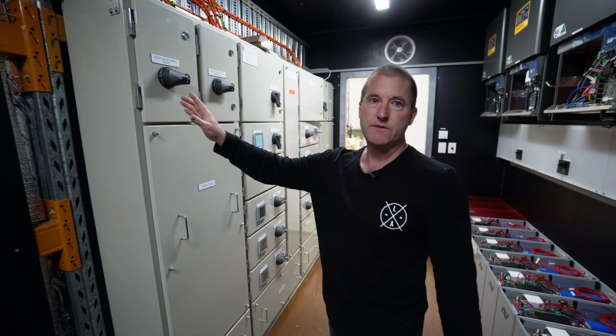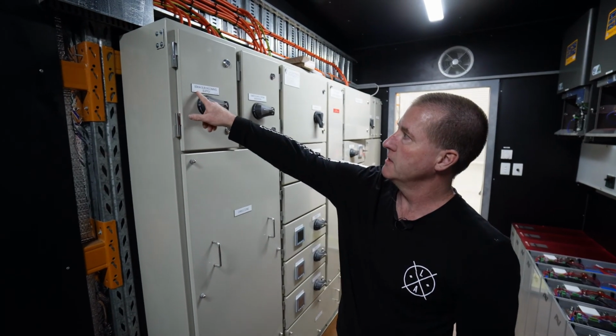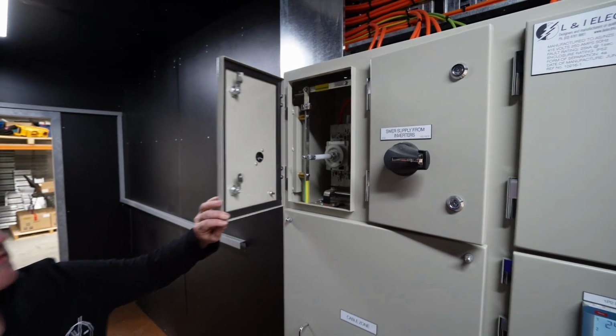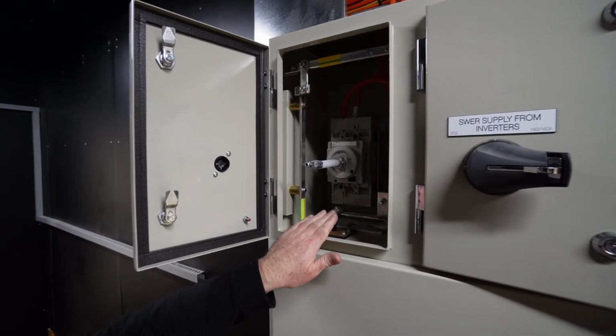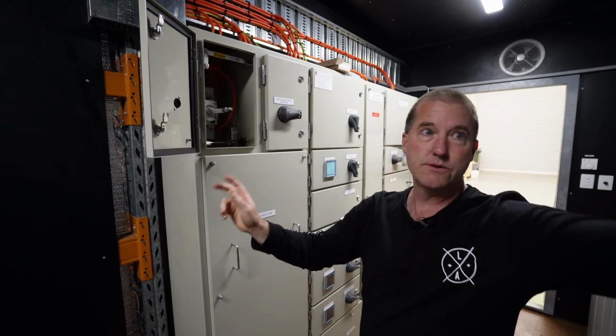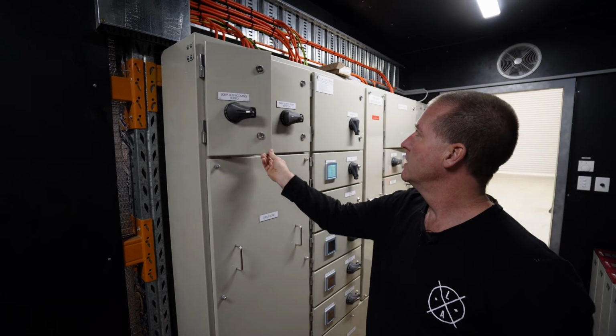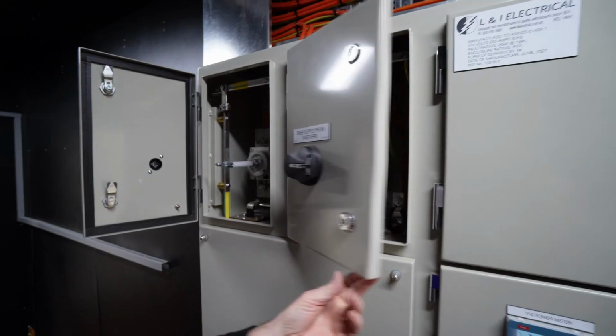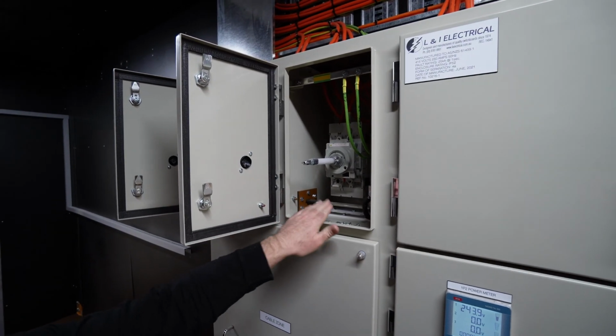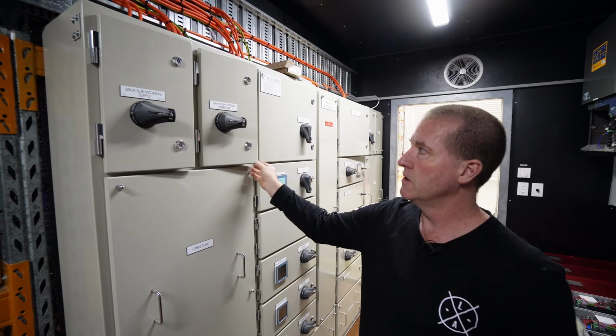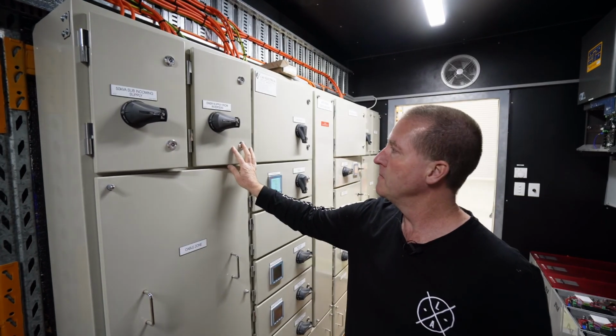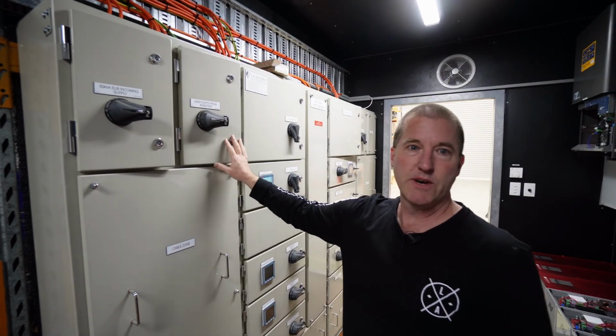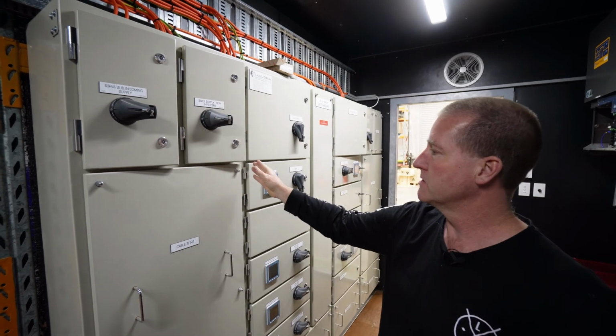I said before that we had a 50 kVA SWER line coming in—that's this one here, the 50 kVA sub incoming line. So 2 phases come in from the grid here, then go out and feed the 2 inputs over here. This is the output from those 2 SWER lines after they've gone through the inverter, so we have blackout protection now on these 2 phases that we didn't have before. They're just spare phases that can be used as single phase feeds around the site.